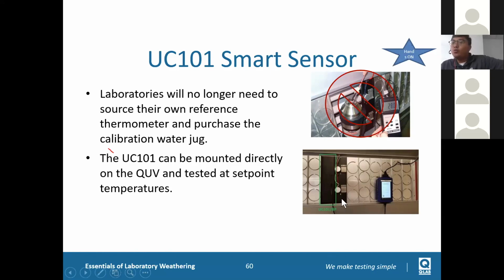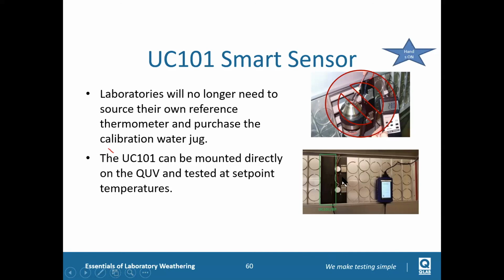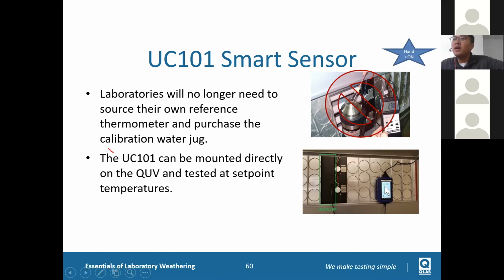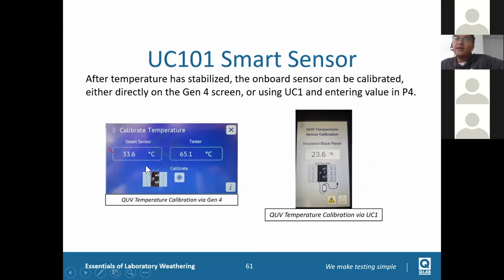But here, guess what? Our temperature sensor for the QUV is in here, right? But right now we have an identical panel. It's exactly the same as the onboard temperature sensor. It's identical. And you put it here. Also use your UC1 system, or if it's a Gen 4 controller, you just need to insert it into your chamber. And when the temperature is stabilized, there's a reading in the UC1 system, and you can manually insert the data into your chamber. So that's done like this.